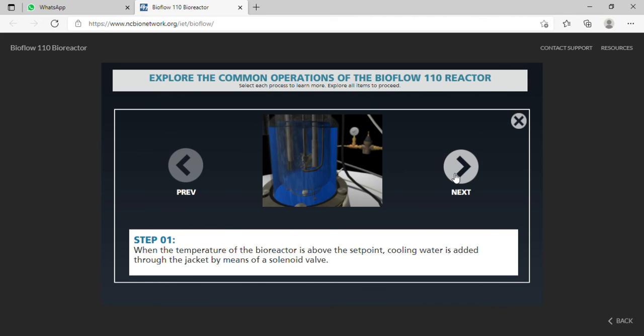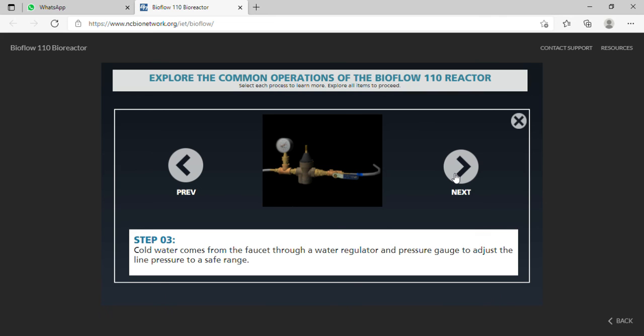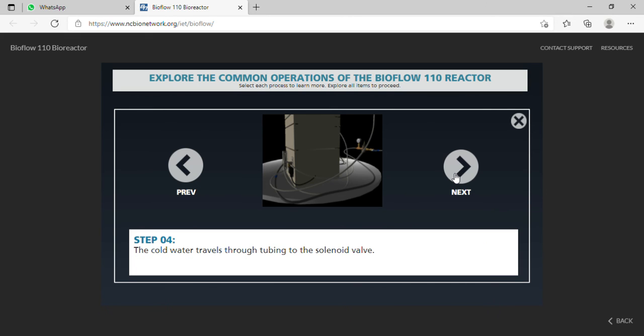Step 1. When the temperature of the bioreactor is above the set point, cooling water is added through the jacket by means of solenoid valve. Step 2. When the temperature is below the set point, the jacket water heater comes on to heat the jacket water. Step 3. Cold water comes from the faucet through a water regulator and pressure gauge to adjust the line pressure to a safe range. Step 4. The cold water travels through tubing to the solenoid valve.